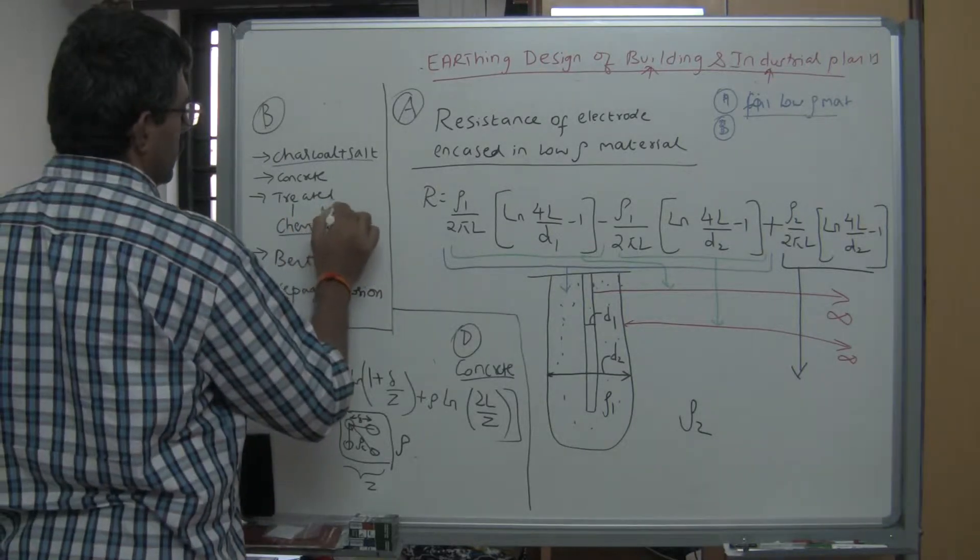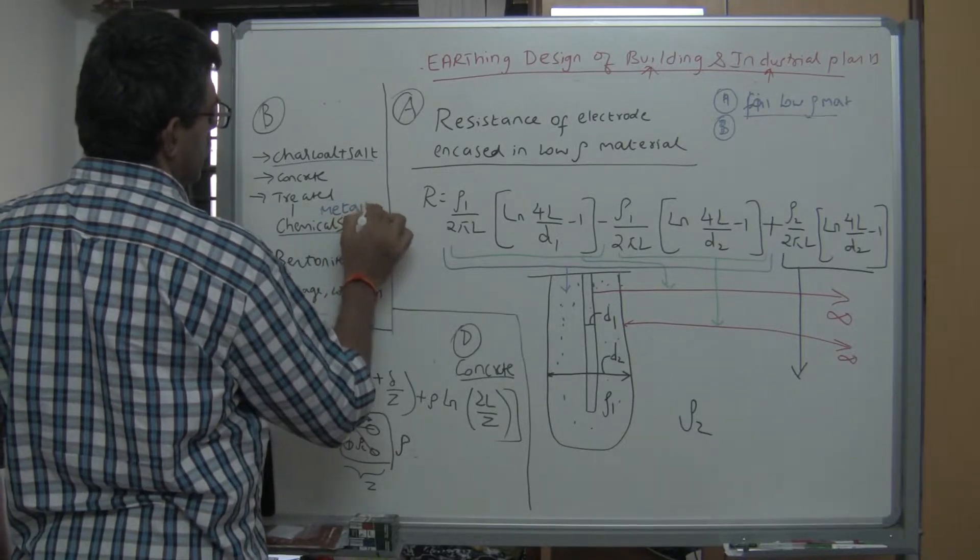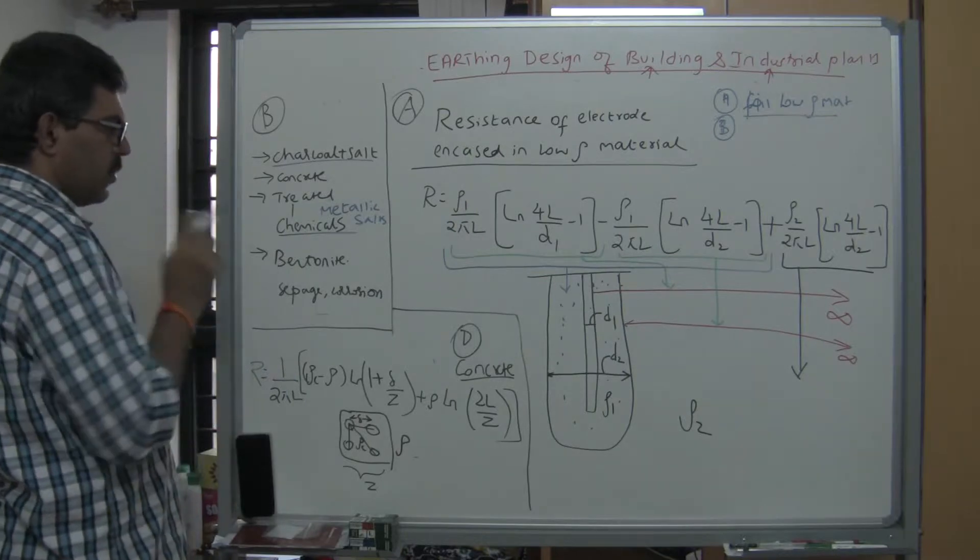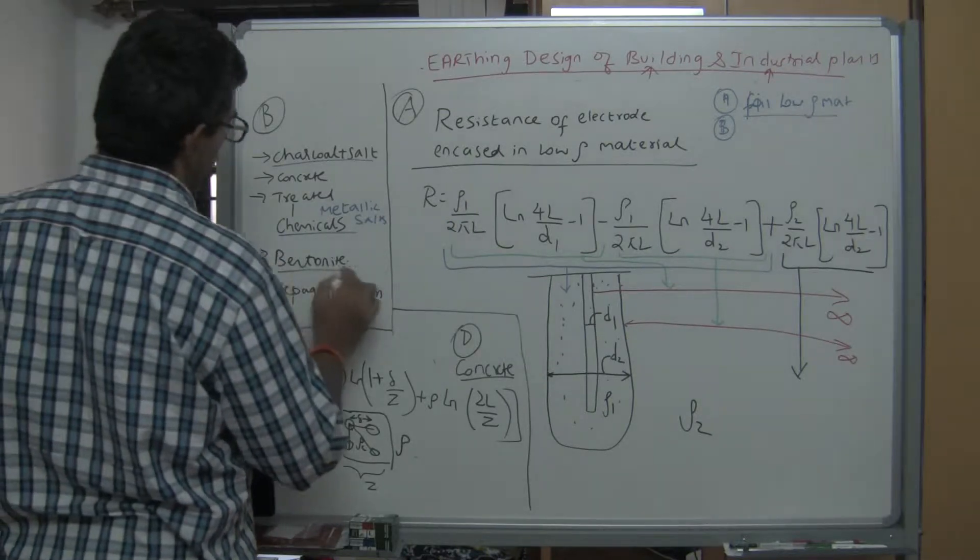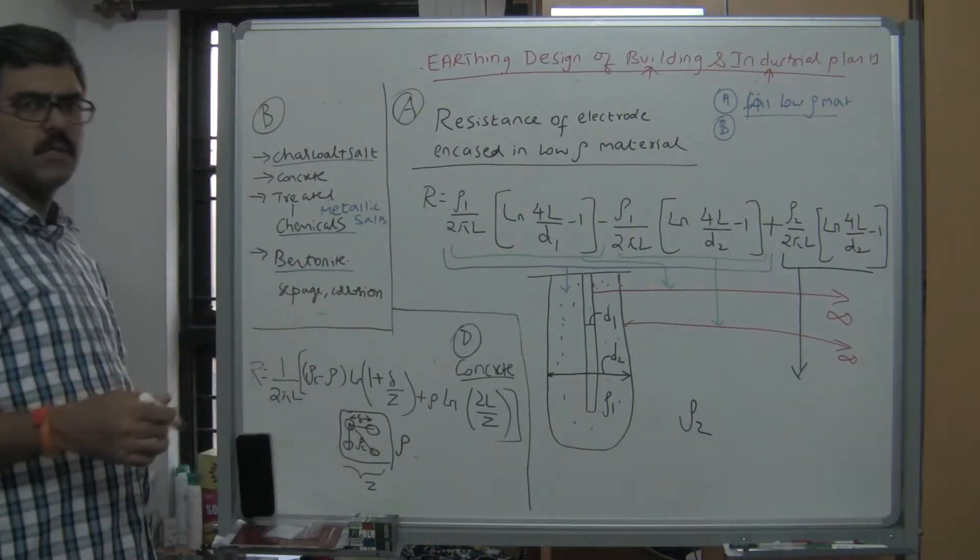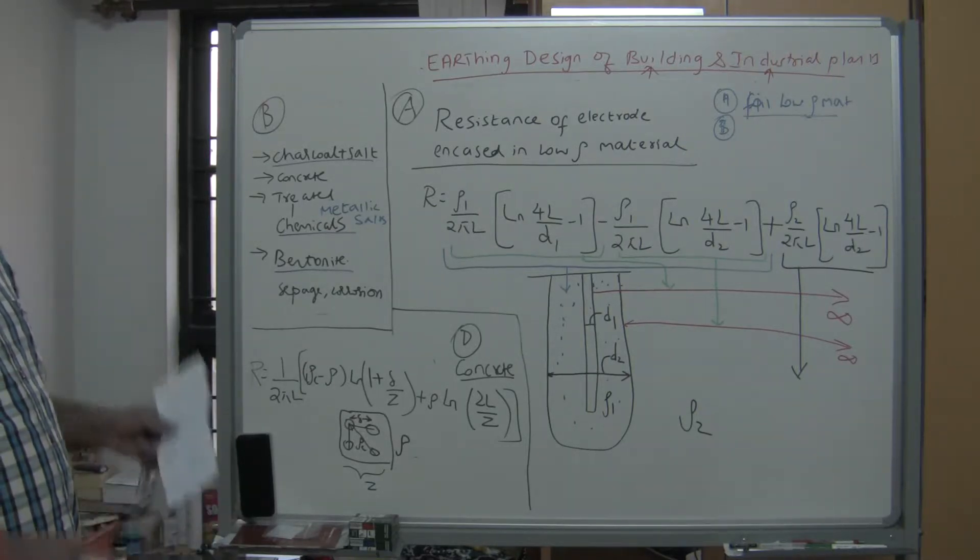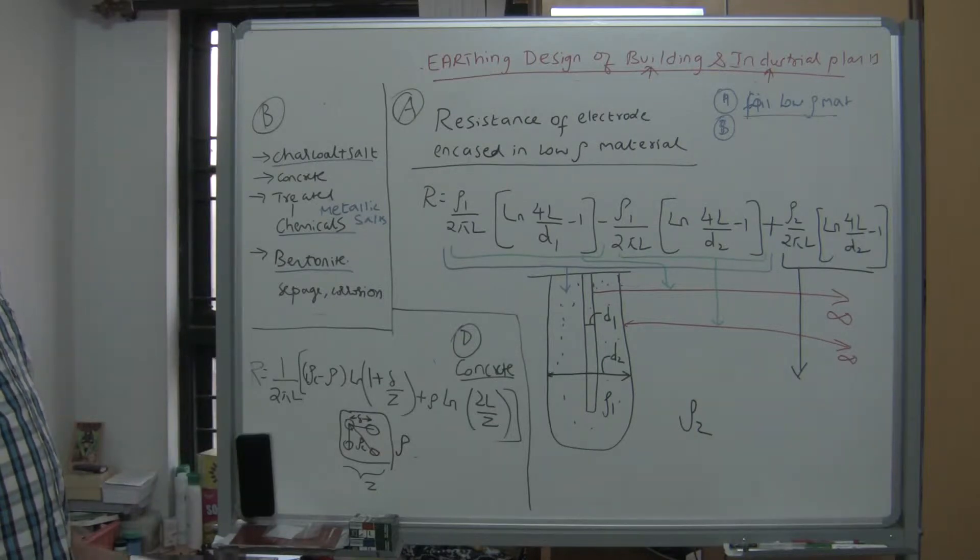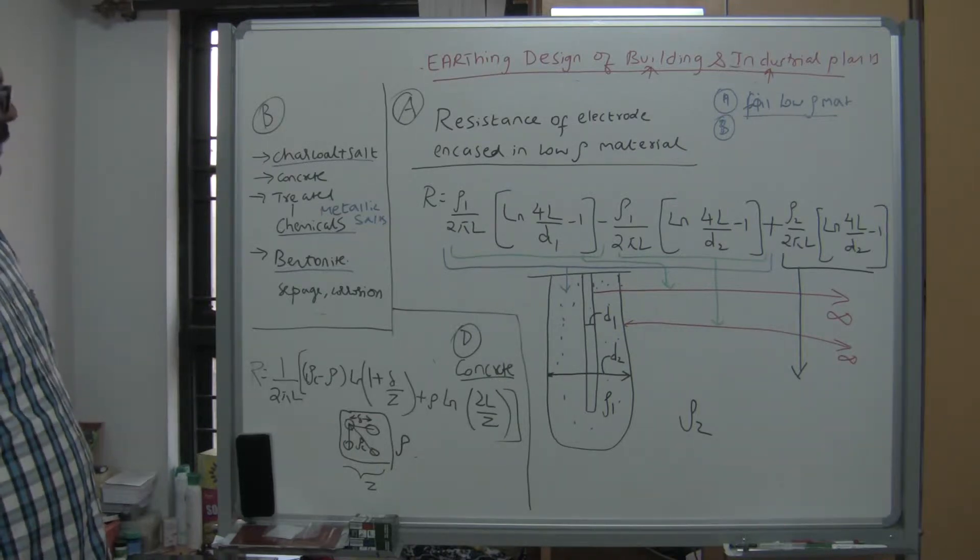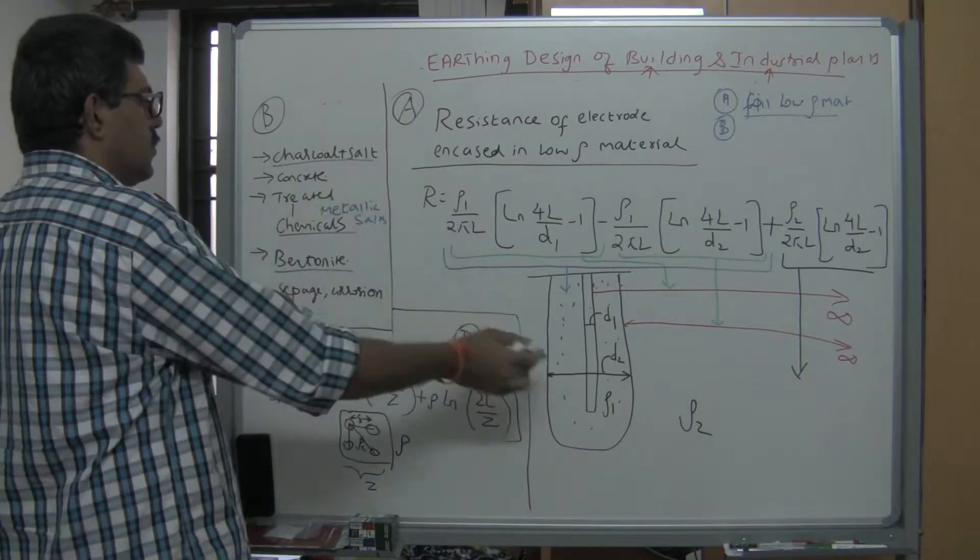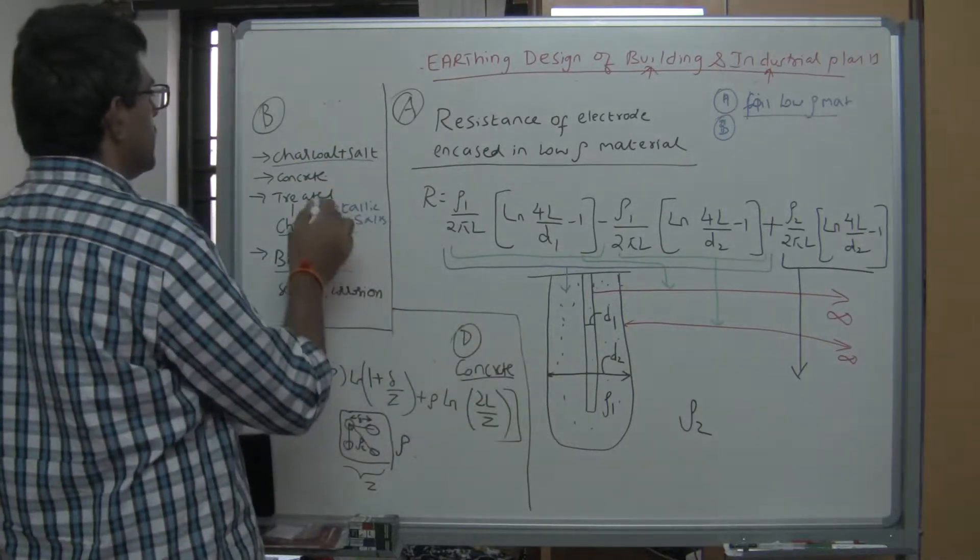One more option is to add bentonite. Bentonite is basically a form of volcanic mud - it has lots of metallic salts naturally in it, so the resistivity will be very low. When you add something around your electrode, we call it a treated earth pit.